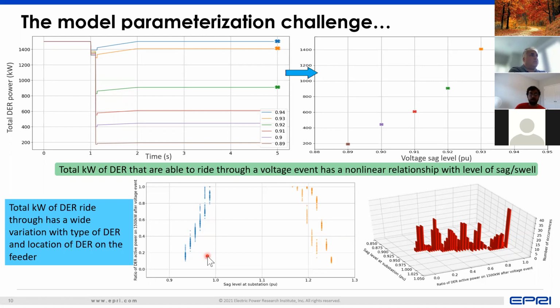So given all of these uncertainties, if we repeat the same exercise with a voltage variation of 5%, going from this one scenario with one configuration of DER, which could be represented by a least squares line, to playing in all of these uncertainties and taking various combinations of the DER location, we get a representation of the trip characteristic in this format. Now you can see the variation at each voltage level. Instead of one single point, you have a host of points aligned at a single voltage level, and the occurrences of tripping have a widely varied representation.